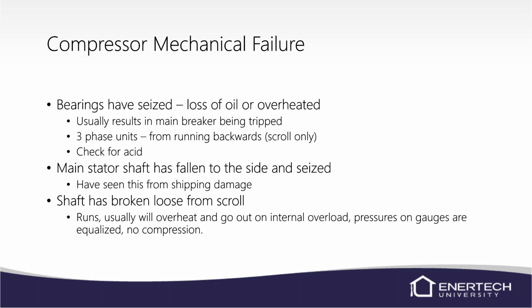The shaft could be broken loose from the scroll. It'll run, but it'll usually overheat and go out on internal overload. And the pressures on the gauge are either equalized or pretty close. We really just don't have any compression. Amp draw, if it's a 4 or 5 ton unit, will probably be like 4 or 5 amps. Normally we're about 15, 17, somewhere around there. So that's a pretty good indication that it's not pumping.